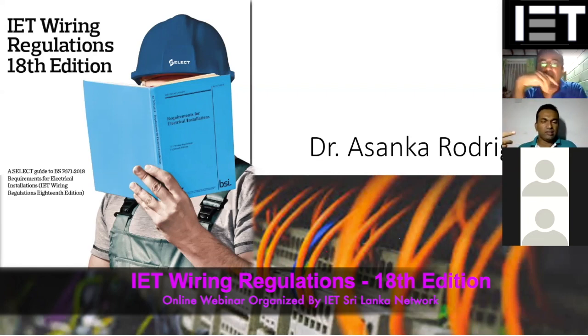One is the ring circuit, and the other one is a radial circuit. When you look at the ring circuit, we have to use either 30 ampere or 32 ampere. Within a 100 square meter area, you can use whatever number of socket outlets. There is no limit, because basically it considers the diversity within that 100 square meter area. So within that ring circuit, you can use whatever number of socket outlets.